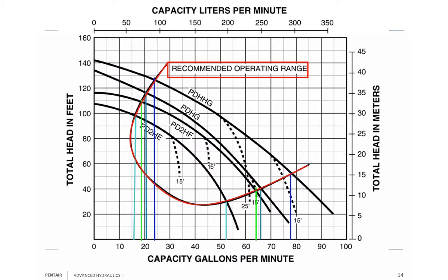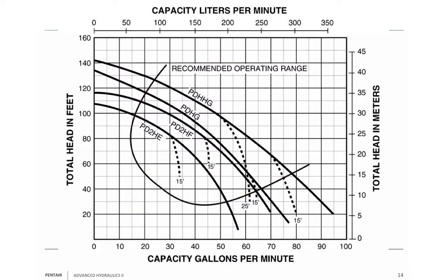Now over here, back to this real curve, I want you to understand that this sometimes gives people a little bit of edge because they can't tell how many feet of head there is. Okay? So here we've got our 2.5 horsepower curve. Our shutoff head is about 142. What that 142 is made of is, let's say, and now if you look down the lower left-hand corner there, you'll see a gray line went right over the red line.